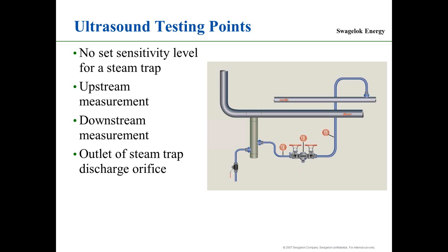How do I get started? You do what I call the comparison method. What I want you to do is go upstream and desensitize the unit till you're down low on the scale. And I have a meter here and a few slides to show you. Then I want to go downstream and make sure that I do not have any competing ultrasound coming to the discharge side of the steam trap.